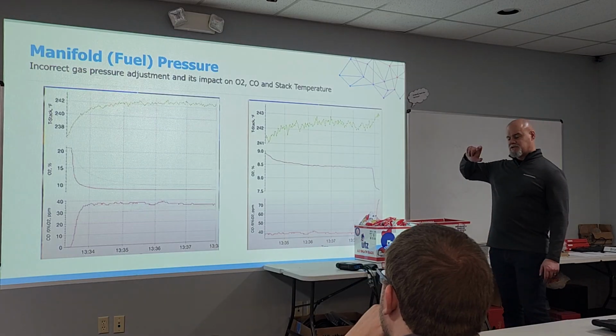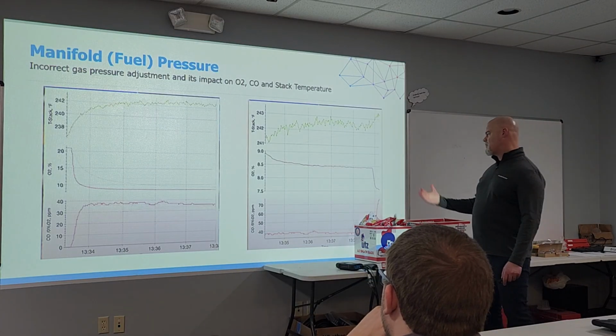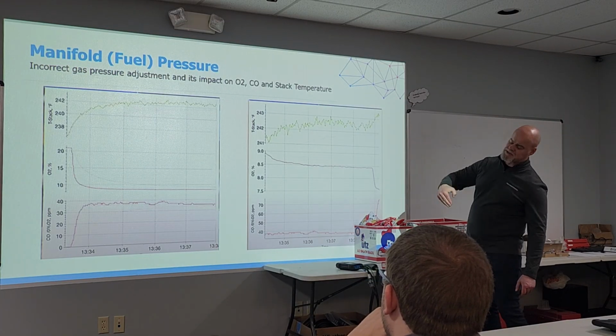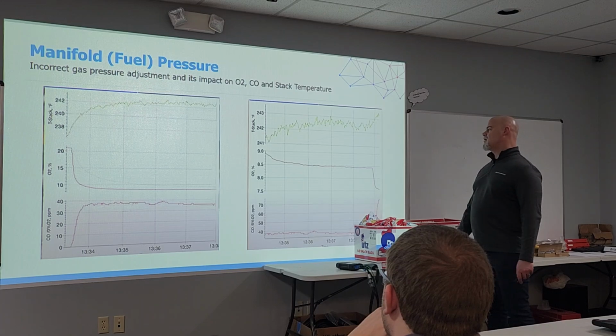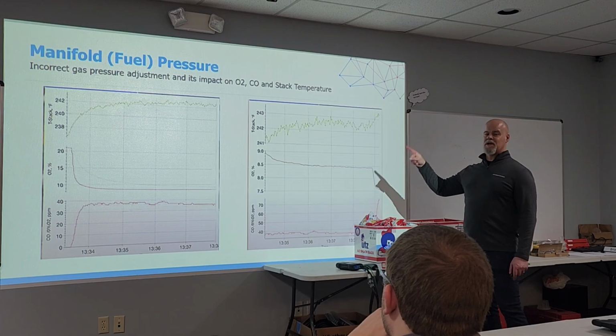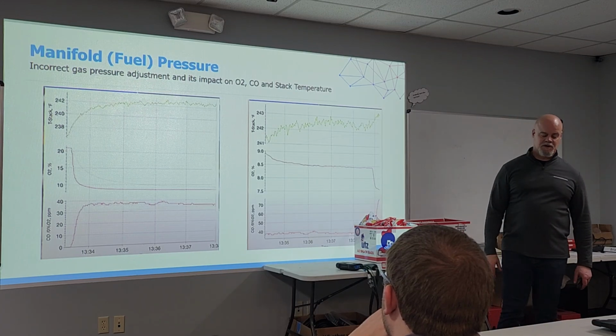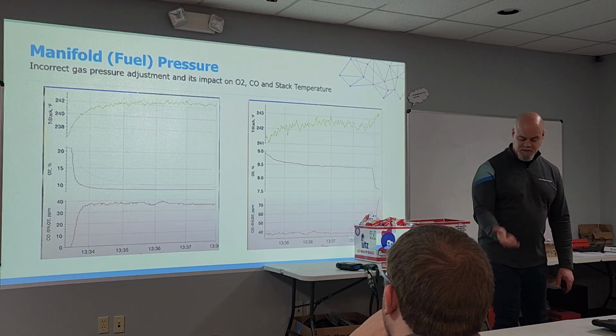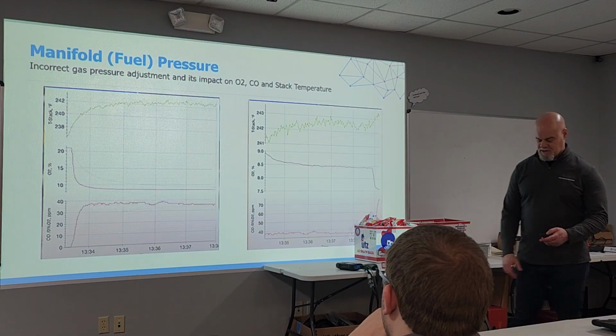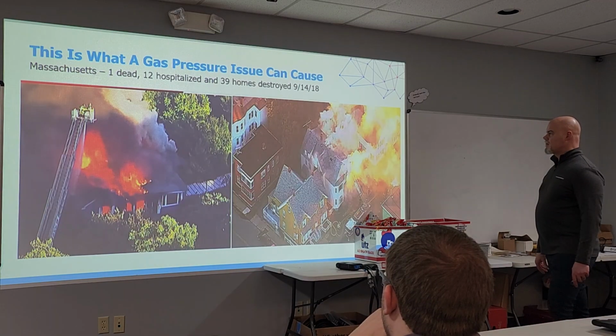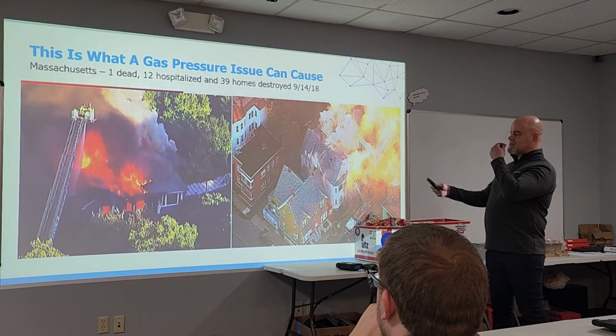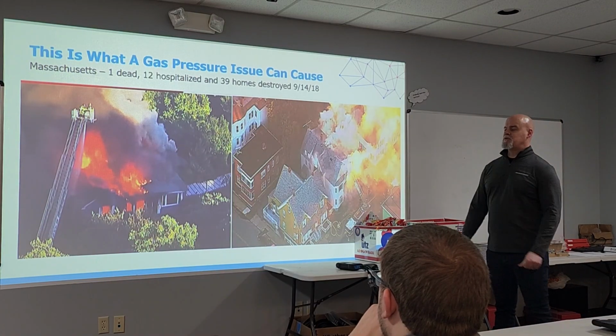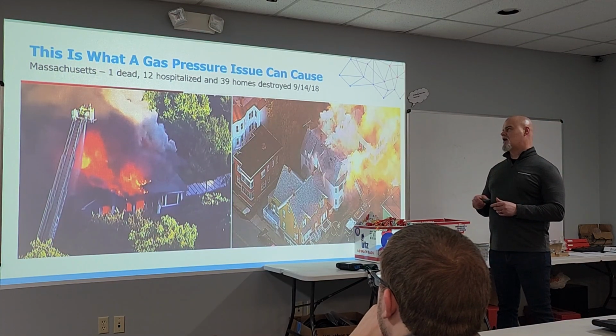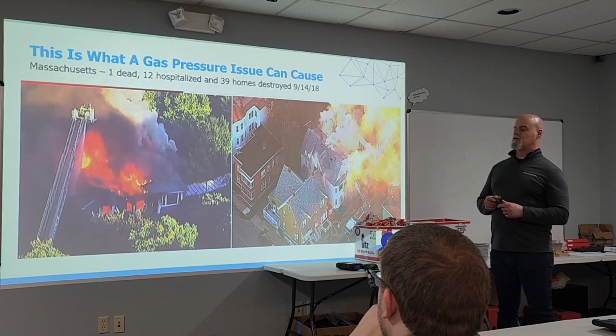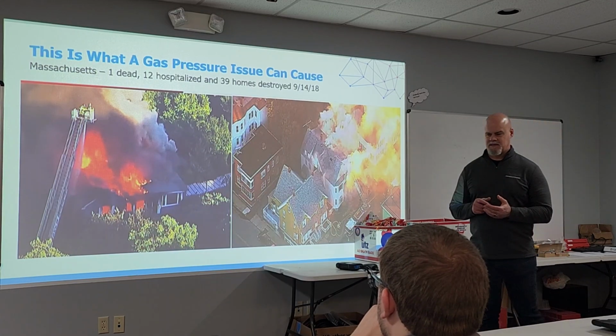So when it makes an incorrect adjustment and dials gas pressure up too much, what happens? CO goes through the roof, oxygen plummets, stack temperature on the rise. If left unchecked or uncorrected, that is potentially going to shorten service life, create a dangerous condition, and it's going to crush the efficiency. It's going to waste money. So what does that mean? That means this. Over here, Massachusetts, 1 person dead, 12 hospitalized, 39 homes destroyed, September 14th, 2018.